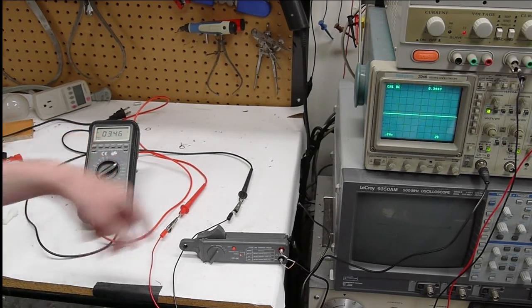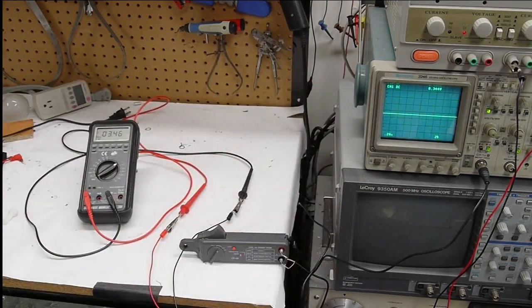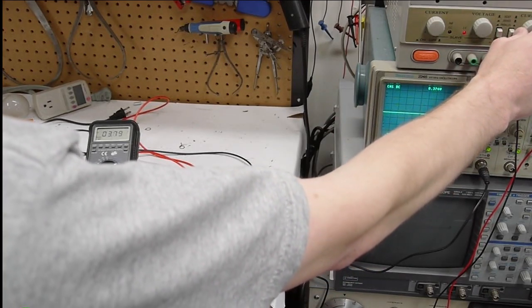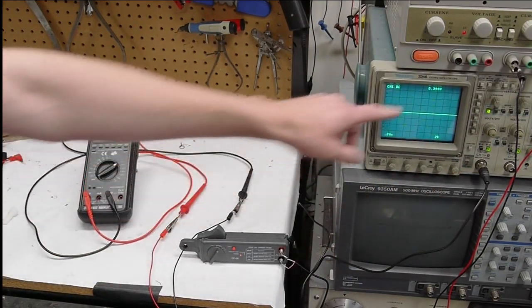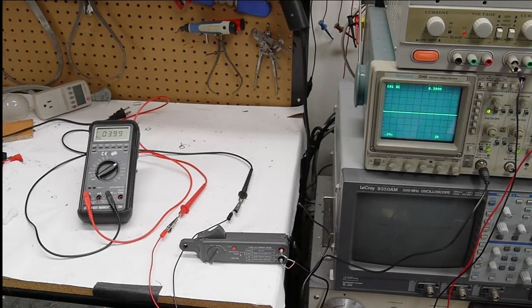So let's see, we've got here 3.46, we've got 0.344, so still pretty close. Just round out this range here. 3.99 and 0.398, so DC accuracy is looking good.